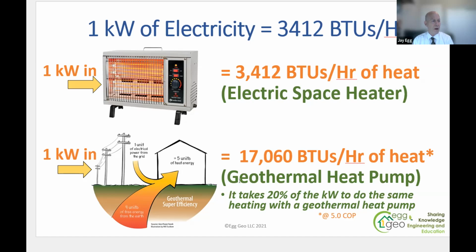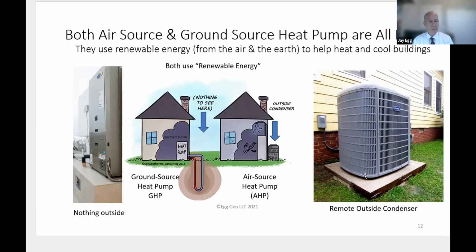So this is such an important part to understand in the geothermal, in the heat pump realm. Now these heat pumps, and you can see the two different types here, air source on your right, and geothermal on the left. It's pretty simple. You either use an air source heat pump or a geothermal heat pump. They're both the same technology. However, with a geothermal heat pump, the outside portion is underground, right? Because it's transferring energy with the underground temperature rather than the outside air. So these are unitary heat pumps usually, and these are split systems usually. There's an outside condenser. So in this unit that you see on the left, it has the complete heat pump, including the compressor, evaporator, condenser, and expansion valve, all in one unit, where this one has two parts because it's transferring heat with the outdoor.